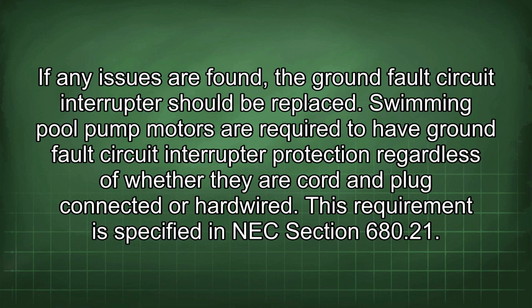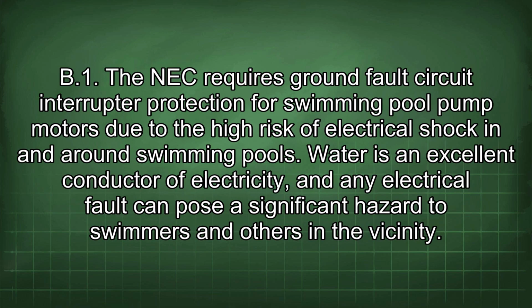Swimming pool pump motors are required to have ground fault circuit interrupter protection regardless of whether they are cord and plug connected or hardwired. This requirement is specified in NEC section 680.21 D1. The NEC requires ground fault circuit interrupter protection for swimming pool pump motors due to the high risk of electrical shock in and around swimming pools.